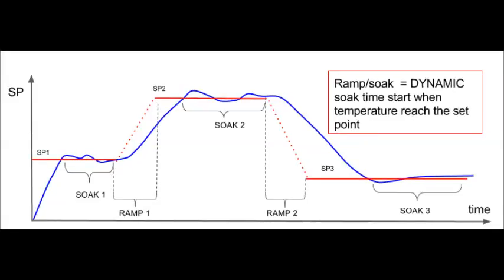In the dynamic execution, the soak time starts when the temperature reaches the setpoint, so it's a synchronous process. Here you can see that soak 2 starts immediately when the current temperature overcomes setpoint 2. These two methods allow you to manage different processes, including processes where the power is not able to follow your setpoint perfectly.